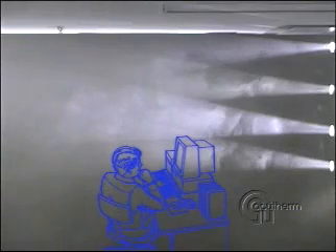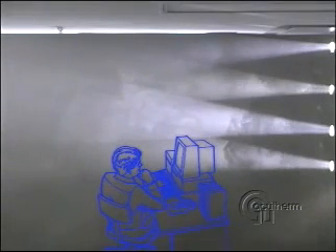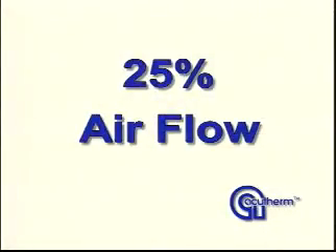In addition to good temperature distribution, good mixing of primary and secondary air also promotes good air change effectiveness. Air change effectiveness is a measurement of how much of the outdoor air contained in the primary air actually reaches the occupied zone, which is the part of the room between 4 inches and 67 inches above the floor. What separates the Thermafuser module from other diffusers is that it can maintain the same air distribution characteristics at extremely low flows.